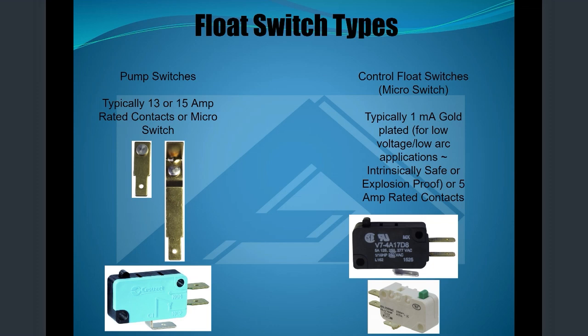It's a 21 amp rated micro switch that we are now using in our ultra pump float switches. And we're rating it to 13 amps. So we're derating it a little, but it will actually handle the full load amps of the pump. But if you do want something a little more robust, you get the Relion, which is the full metal contacts that'll handle that big inrush of current a lot better. And then on the right, a couple different micro switches. On the bottom right is the 1 milliamp, our gold control switch, which can control a lot lower amp circuits, and as well as DC voltage.